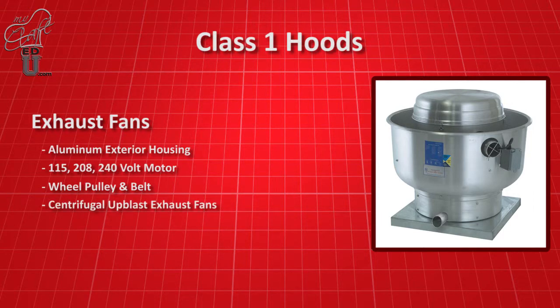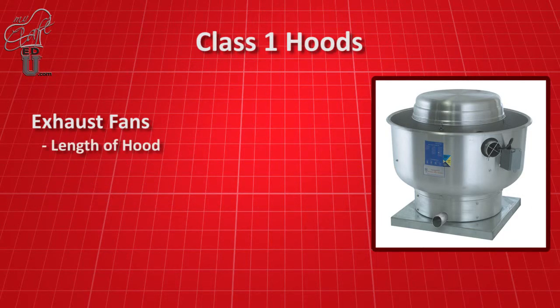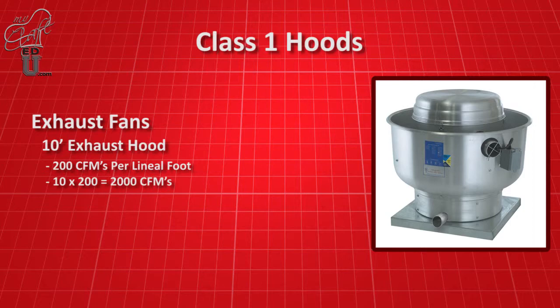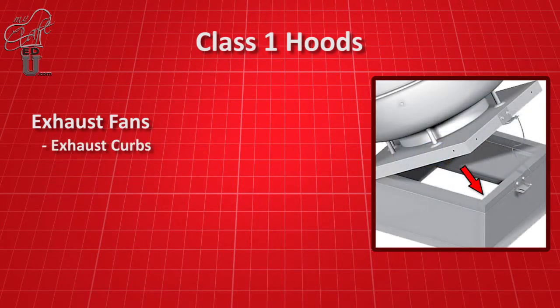These fans are commonly called centrifugal upblast exhaust fans. The size of the exhaust fan and CFM is determined by the length of the exhaust hood. Exhaust fans can extract from 150 to 600 CFMs per lineal foot of hood. So, for example, a 10-foot long hood with 200 CFMs per foot of hood would require a fan that produces 2,000 CFMs. Exhaust fans are mounted on a curb, which is attached to the building.